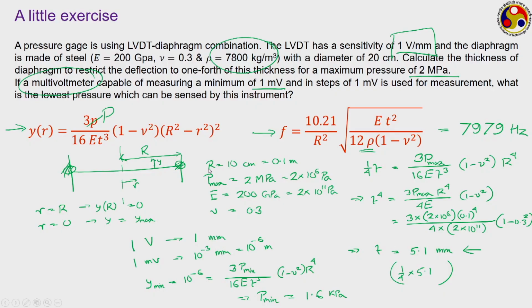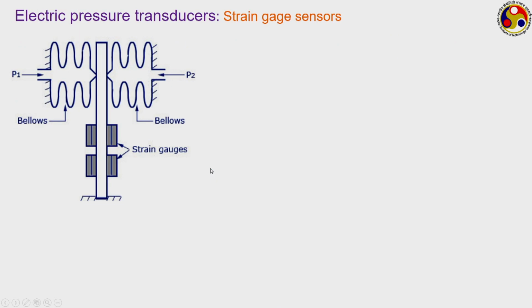It is only because of your secondary transducer that you are getting an electric output, and the secondary transducer is a deflection measuring instrument like an LVDT or maybe a strain gauge or those kinds of instruments. So, we should not properly call it an electric pressure transducer, but there are a few examples where a similar kind of situation arises and we still call it an electric pressure transducer, like the first one that we have here.